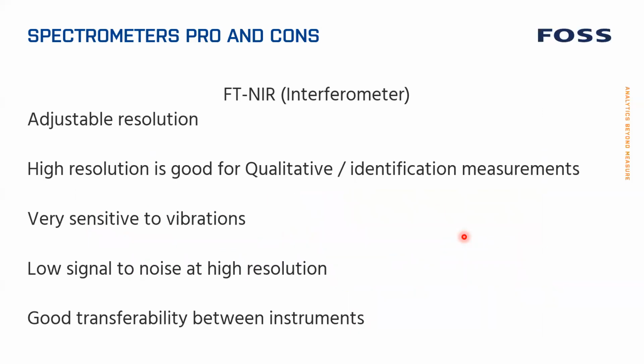A little about interferometers or FT-NIR. They have an adjustable resolution. For the monochromators, the resolution is fixed, but for the FT, you can actually change it. High resolution is good if you want to do qualitative or identification measurements, which in principle we don't. We have the possibility to do it, but we haven't focused so much on it. NIR is not really good for that. Mid-infrared is much better.